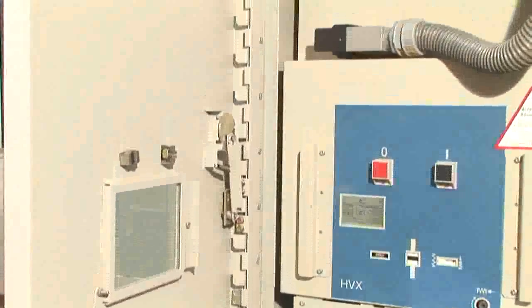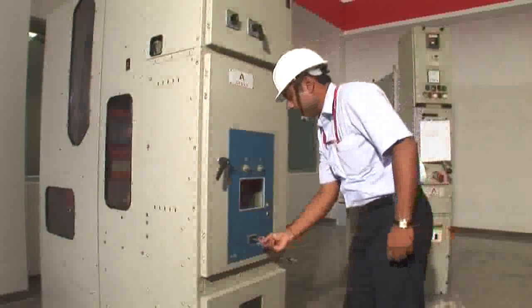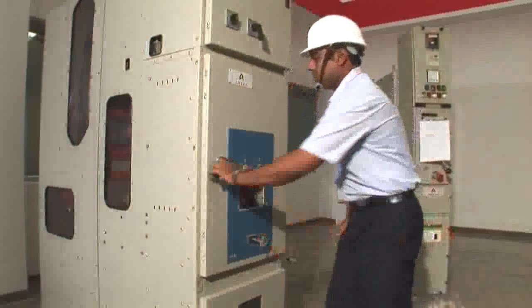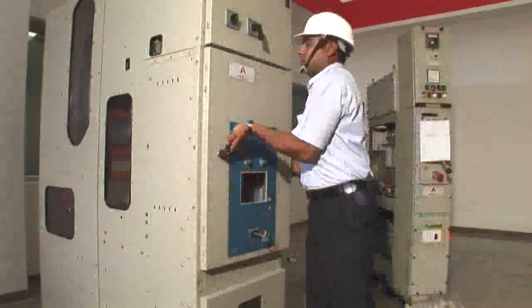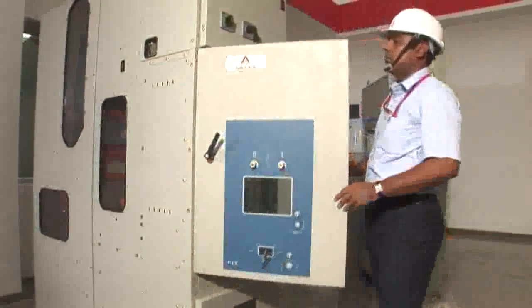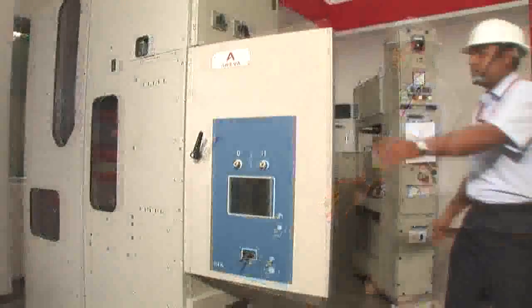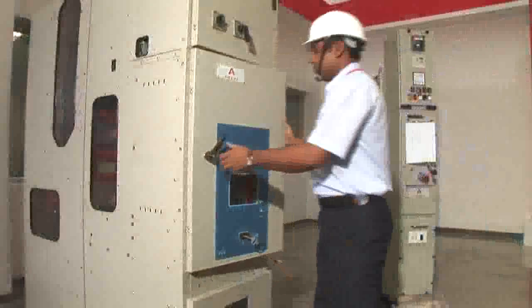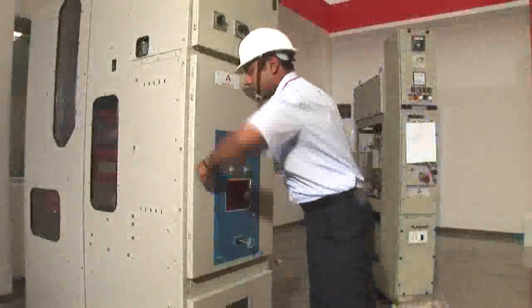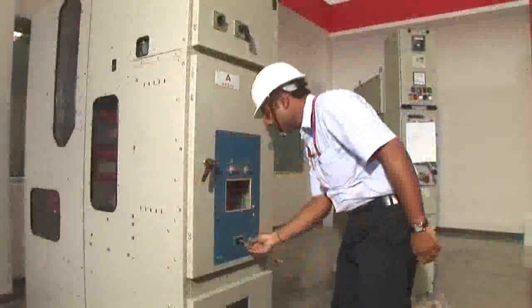Still, there's a catch. Take the example of a door, which is a very important part of the enclosure from the point of view of protection of the operator from arc faults. It may happen that a particular door has been type tested with many screws securing it to the cubicle, but is practically unsafe, as in a real-life situation any operator would be reluctant to secure too many screws on a part which he may need to open often. The door has to be like a refrigerator door, which could be easily latched.